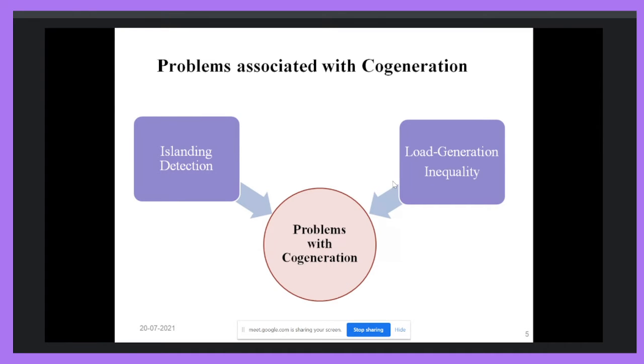Suppose an industrial system is interconnected with the utility grid to fulfill its mismatch in load and generation. The industrial system, which has its own generation, is connected with the utility grid to balance its load and generation. But whenever there is a problem in the utility grid, suppose a short circuit fault, we know that a short circuit fault is associated with a decrease in voltage, an increase in current, and a decrease in frequency. So due to the fault, the system voltage will reduce, frequency will reduce, and the current will increase in the utility grid.